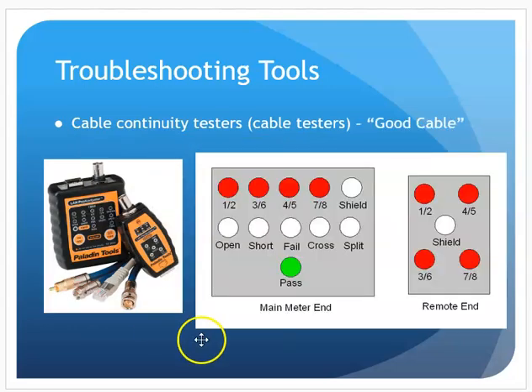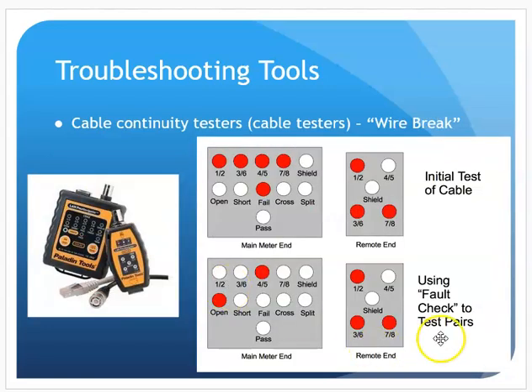So ideally, when I test it, I see all 4 wire pairs are connected and it'll show up that it's passed. And the other end shows up the same thing. That's what I would see on this end over here. If I have problems, though, and this one actually has a fault check button, I can go through and start checking each wire pair to let me know if there's an issue.